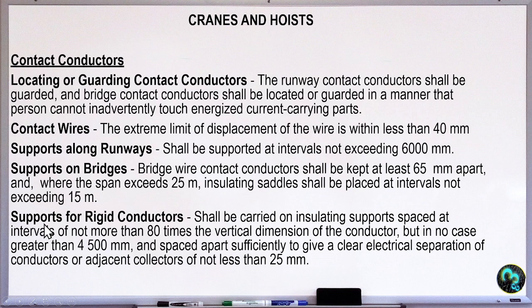Yeah. Support of rigid conductors shall be carried on insulating support space at intervals not more than 80 times the vertical dimension of the conductor, but in no case greater than 4,500 mm, and space apart sufficiently to give a clear electrical separation of conductors or adjacent collectors of not less than 25 mm. So ang separation between conductors is not less than 25 mm.